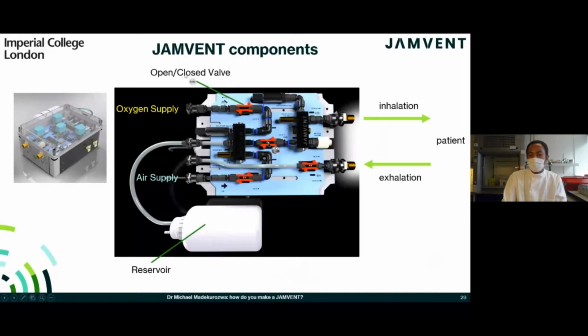We have open or closed valves here, here, here, and here. With these valves, a small circle denotes the valve being closed, and no circle denotes the valve being open. In this case, the valve is open, so oxygen moves through the system to the reservoir, but it won't go down further because this other valve is closed.